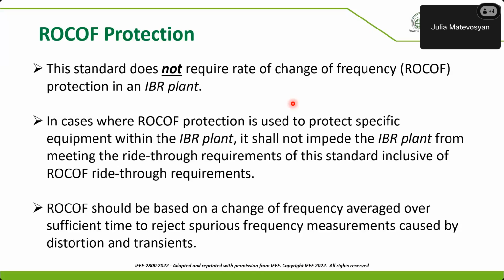Frequency measurement itself, forget about ROCOF, needs to be done over a few cycles. There is enough literature out there that talks about how to reliably measure frequency, so we call that out again. ROCOF should be based on change of frequency averaged over sufficient time so that you can reject bad measurements caused by distortion and transients.